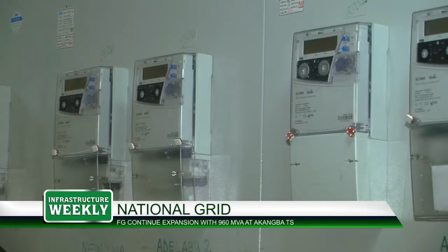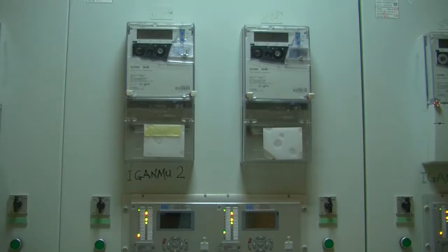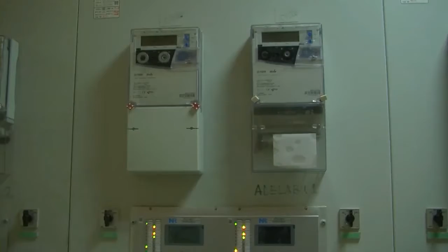He added that the improvements have helped in enhancing operations and safety of personnel in the transmission station. Contact is reduced because I send a closing input or opening input into the system. I don't have to go to the equipment like in the past, because now since it is automated, we operate from the system and just make a confirmation. I can stand at a distance and check that the switching I carried out has been obtained, so I don't need to go close to the equipment again. We operate through the SCADA system right from the control room, and when you do that, you only go outside for confirmation.